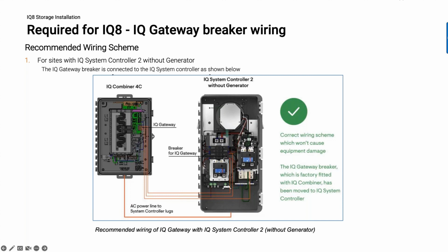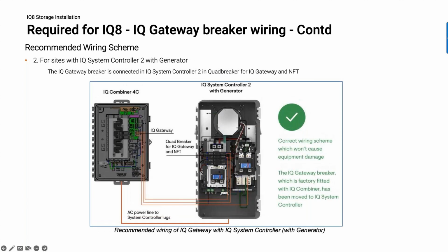There are, of course, customers that are installing the generator, and so you were saying, what do I do now because I don't have that breaker slot? So the second option then is that there is a quad breaker available for where the neutral forming transformer, the NFT breaker is. You would essentially just replace this NFT breaker, which is a 2-pole breaker, with a quad breaker, and the quad breaker will feed the neutral forming transformer and can feed the IQ gateway as well. Okay, so that's two options there.